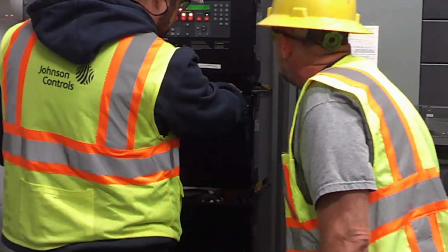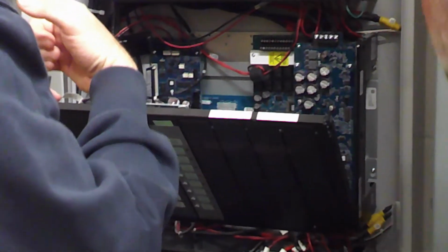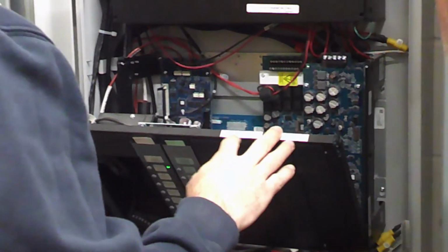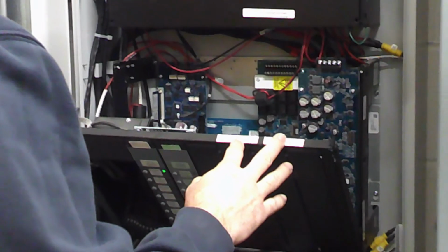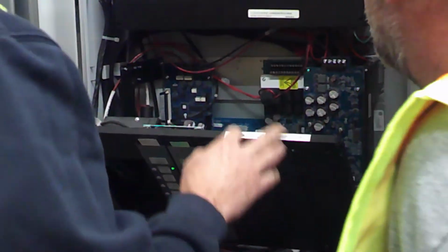Right here, this is probably something you're going to want to know. This is your aux 4 or signal 7 for your water flow bell. That's basically if somebody's going to be doing sprinkler testing, you're going to want to be able to log in and disable this point, because even if you have your speaker strobe bypasses on, the bell is a separate point, so you're going to want to be able to turn this off just so the exterior.